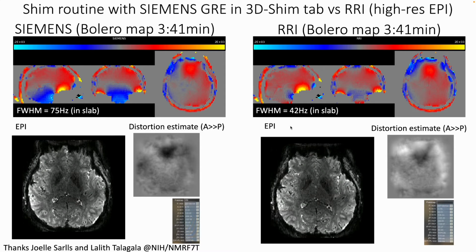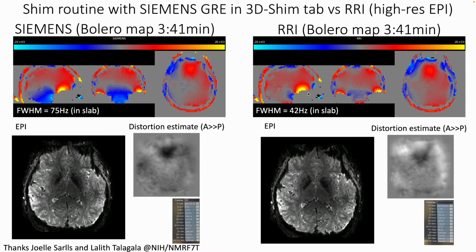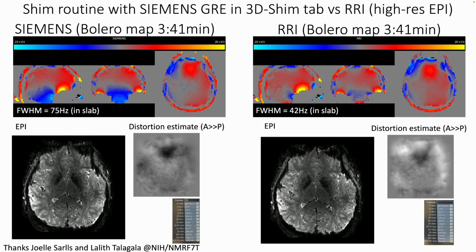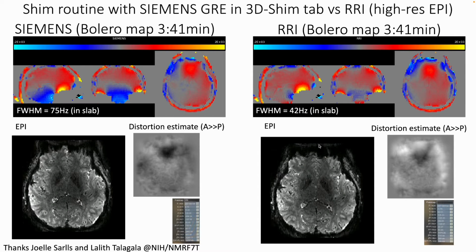The shim tools from our Siemens vendors appear quite outdated compared to the solutions of the academic literature out there. And there's this well-reported issue of having this weird gradient residual in this anterior-posterior direction over there. So we tried to see if we can reduce these effects of the distortions by using the advanced shim software from Resonance Research Inc., which indeed got rid of these gradients up there. However, it turns out that there's also maybe a tiny bit of compromise, specifically at this prefrontal cortex over here, that looks like there's even more of a distortion field in front there.